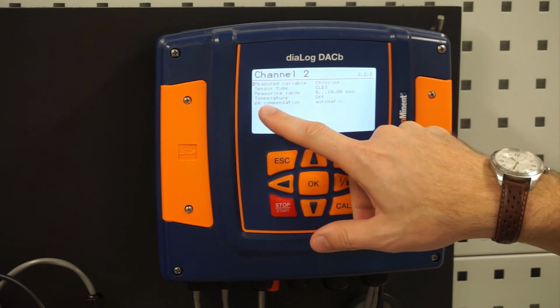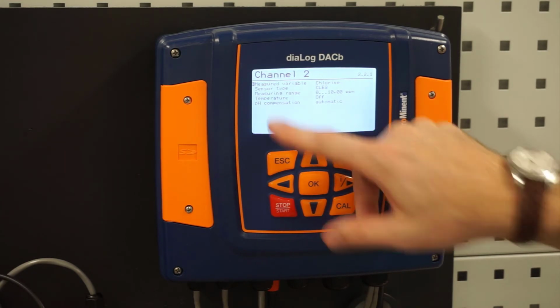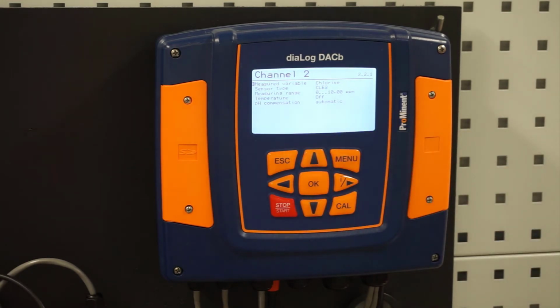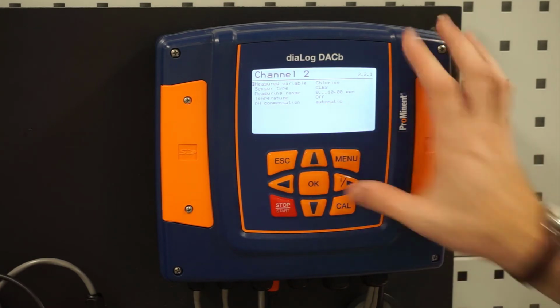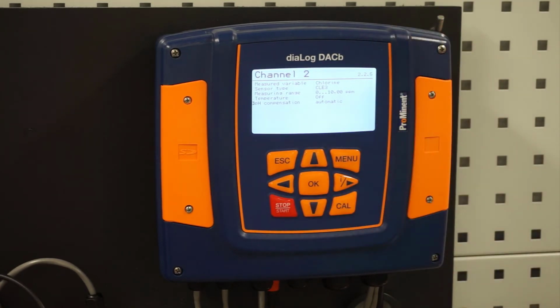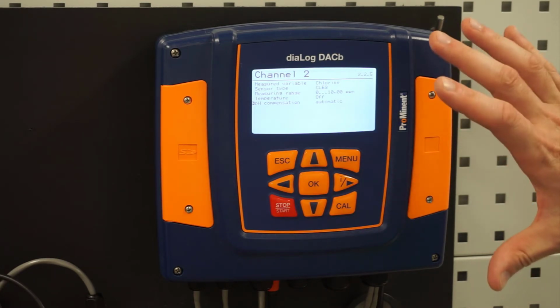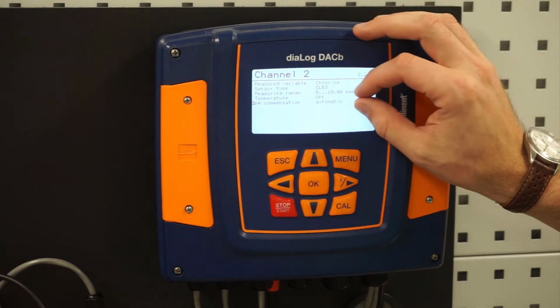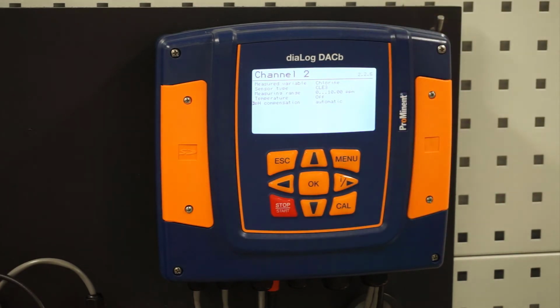Next important thing is to make sure if we're doing free chlorine, we need to have a pH sensor like we do in this case. And you'll need to go down and turn that on so it's on automatic. We'll program that from the factory for you, but it's good to go in there and make sure it's actually turned on.